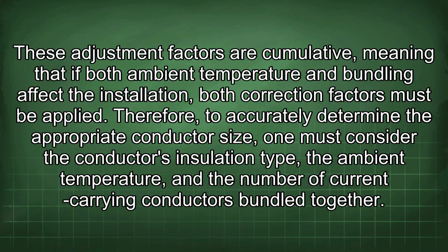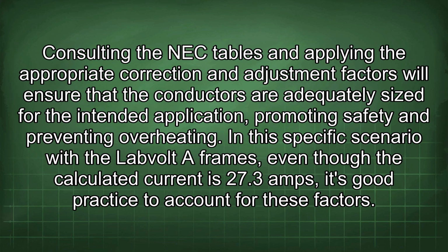Therefore, to accurately determine the appropriate conductor size, one must consider the conductor's insulation type, the ambient temperature, and the number of current-carrying conductors bundled together. Consulting the NEC tables and applying the appropriate correction and adjustment factors will ensure that the conductors are adequately sized for the intended application, promoting safety and preventing overheating.